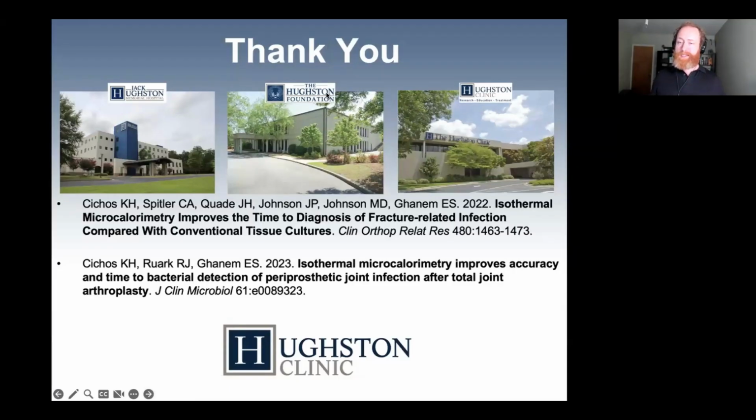Why did you select 10 microwatts above the baseline as the criteria for positive samples? And is the background noise with clinical samples higher than you would get with media alone? We selected 10 initially because the few prior publications before we started our work that used calorimetry, using a different calorimeter to my knowledge, used 10 as the baseline in their work, and we felt like we would at least start with that.